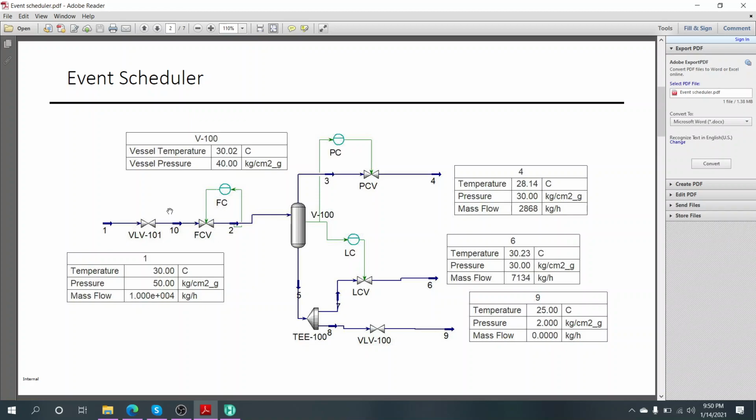Yeah, exactly. Typically you will see in the field that it has to be separate, because this is for safety. This is for the basic process control system, or BPCS. We cannot use this as a safety, because it has to be an independent protection layer. So this has to be an independent system compared to this one. All right. Okay. Any other questions?